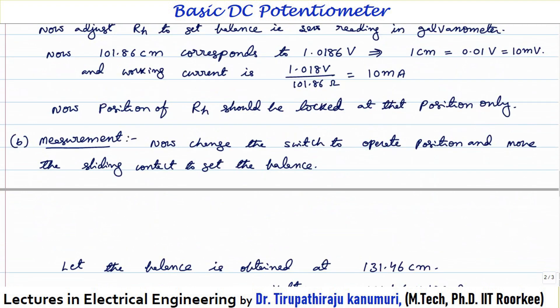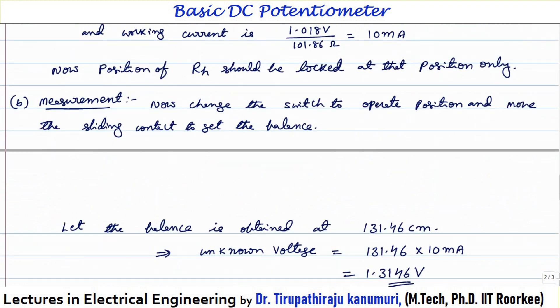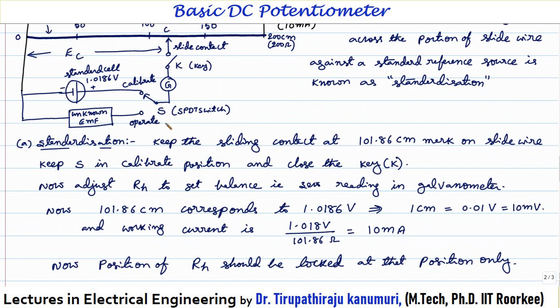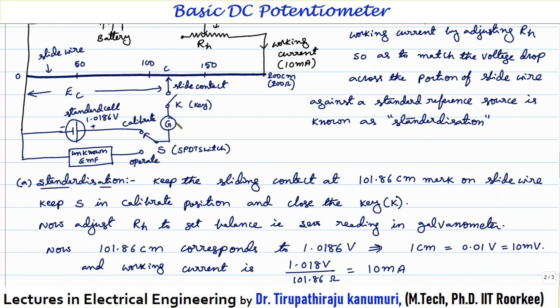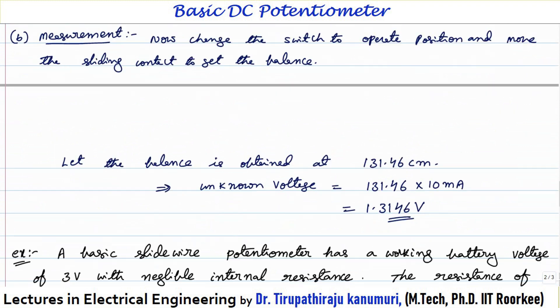Once standardization is done, we proceed to measurement. Change the position of switch S to the operate position. The galvanometer will show a non-zero value — either positive or negative — depending on the unknown voltage. Adjust the slide wire contact in such a way that it shows zero reading. Let us assume balance is obtained at 131.46 centimeters.